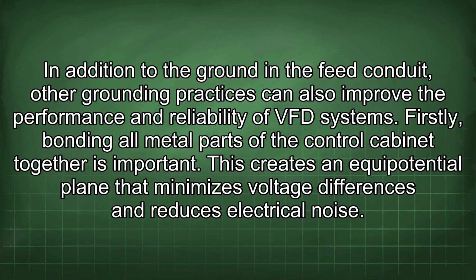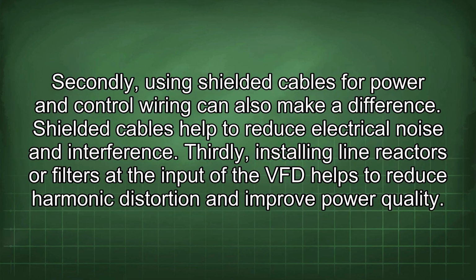In addition to the ground and the feed conduit, other grounding practices can also improve the performance and reliability of VFD systems. Firstly, bonding all metal parts of the control cabinet together is important. This creates an equipotential plane that minimizes voltage differences and reduces electrical noise. Secondly, using shielded cables for power and control wiring can also make a difference. Shielded cables help to reduce electrical noise and interference.